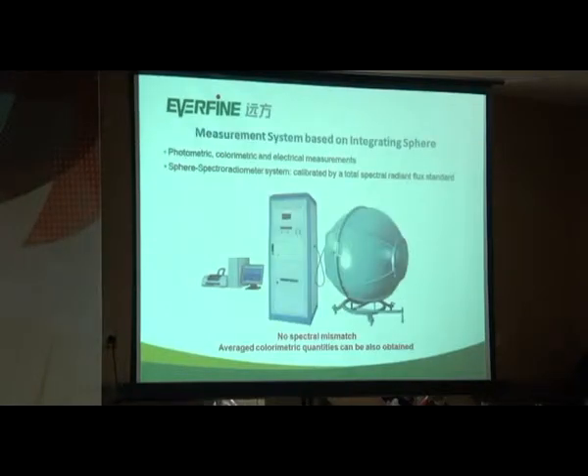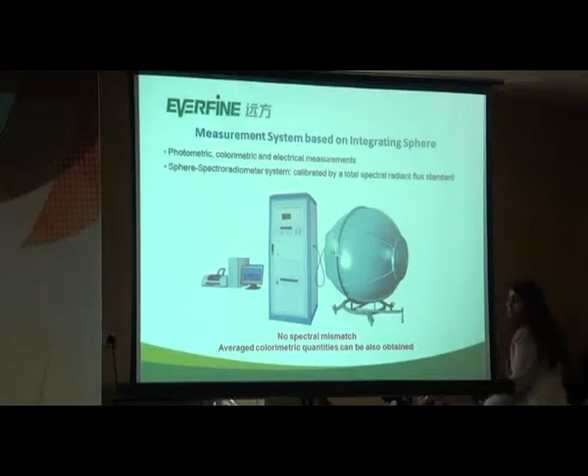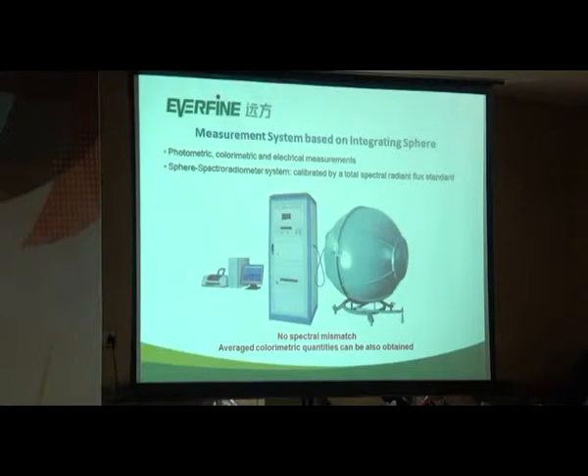This is an example of an integrating sphere system. It consists of a sphere and a spectral radiometer — we call it a sphere-spectral radiometer system. This system has an advantage: there is no spectral mismatch in the measurement result, which is very important. Besides, it can also measure average colorimetric quantities.